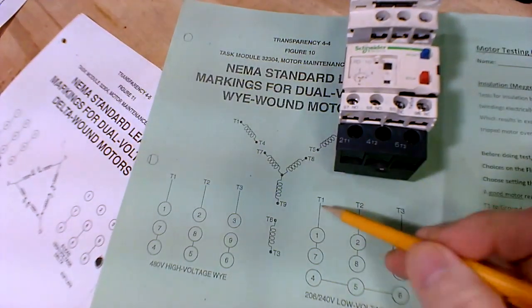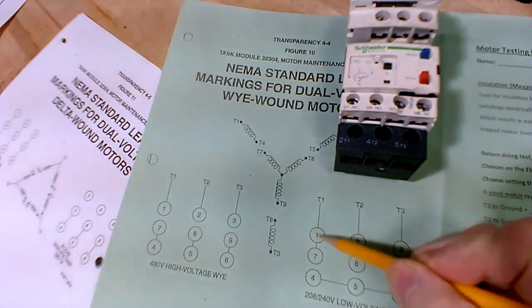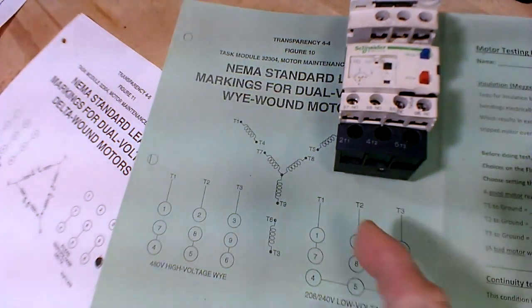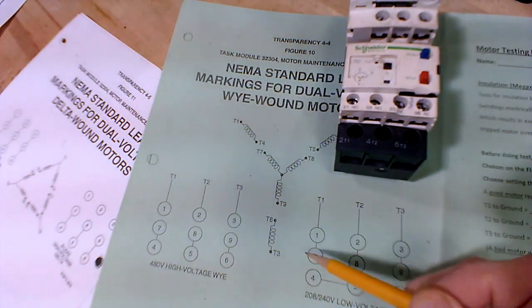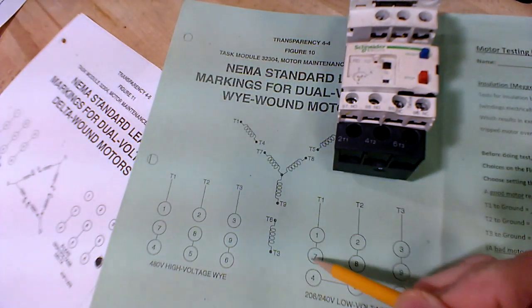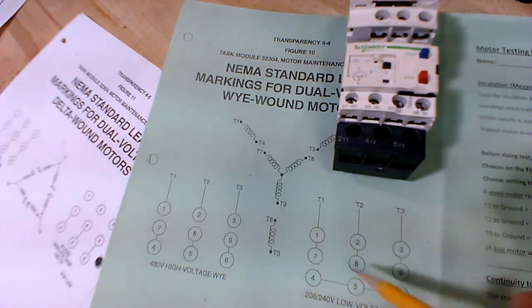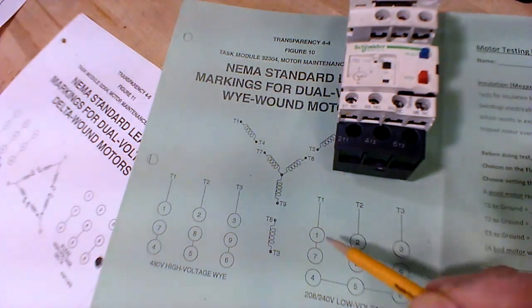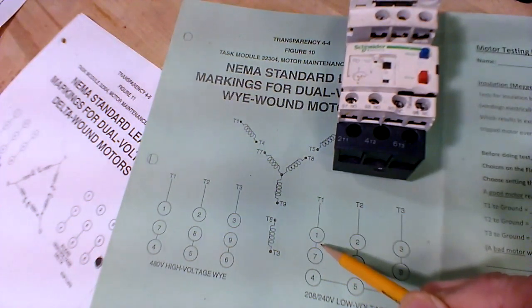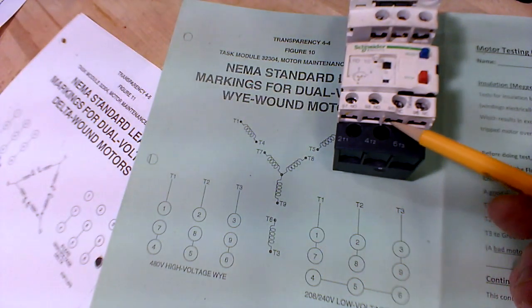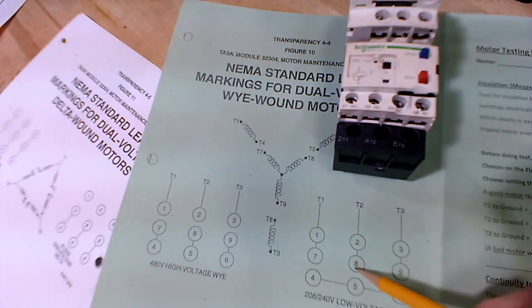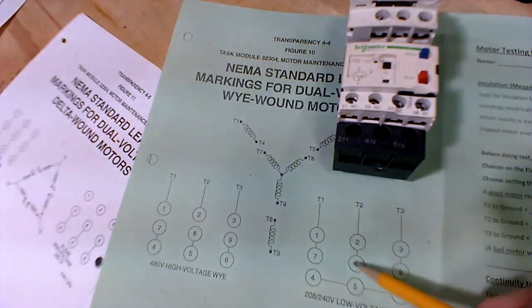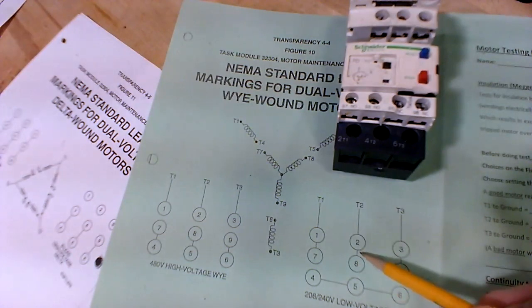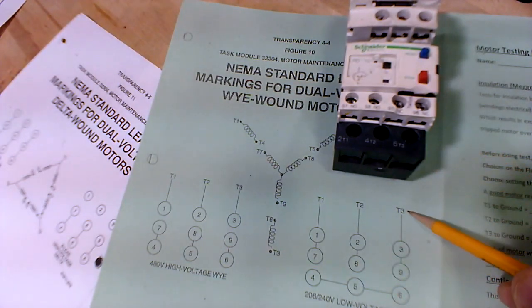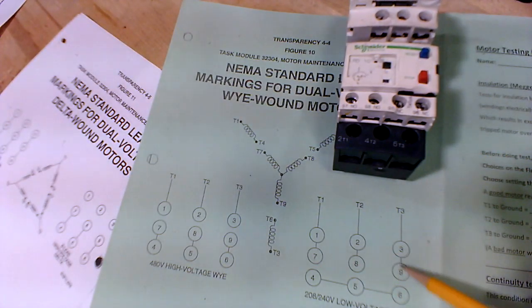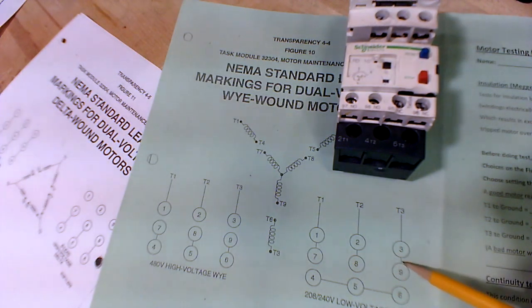You're going to go from T1 to wire number 1 and 7 at the same time. So you're going to have a wire coming from here. You're going to take a wire nut and join this wire with 2 more wires that are in the motor. So 1 and 7 are labeled in the motor cat head. That's going to give you a total of 3 wires in that wire nut. The T2 leg from the starter is going to come in and join with 2 and 8 in the motor. That gives you 3 wires in the wire nut, right? Then you come from T3 on the starter, and it joins with 3 and 9 in the cat head. That gives you 3 more wires.